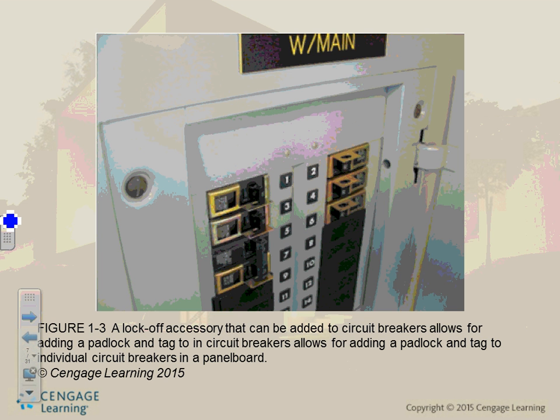So for this circuit breaker, if I want to change the ballast on that one, these ballasts guys are required by law right now to have a disconnect on them, so it's easier. So the new ones, you disconnect them, you change them. But if they don't have a disconnect and you want to work on them, you can add a lock right into this circuit breaker. You go turn the circuit breaker off, put your lock on it, go change the ballast. That's the rule. So you can add locks to an existing panel.